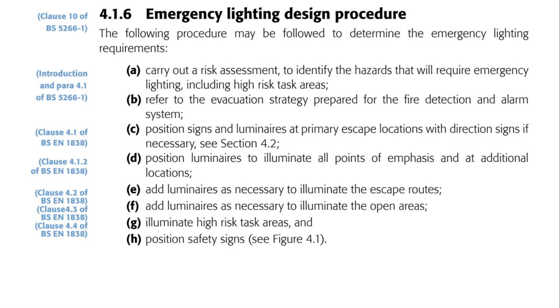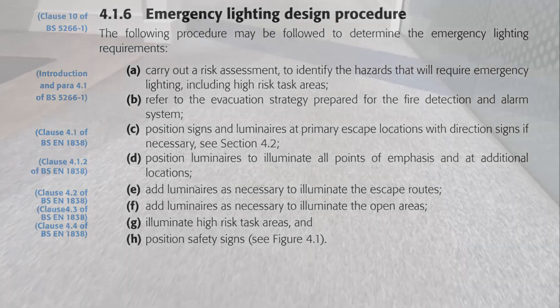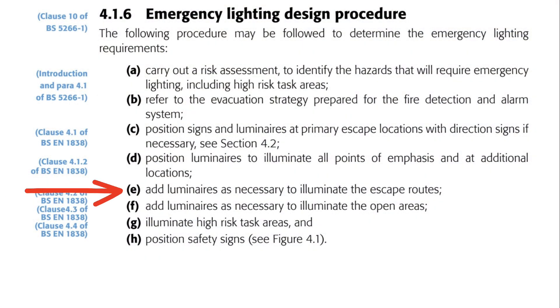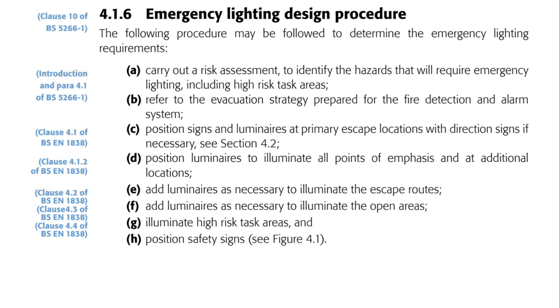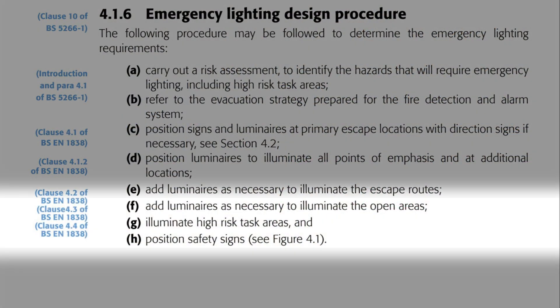Speaking of escape routes, that brings us back to the design procedure. Escape route lighting is critically important, but we only add it after the other elements because once those are placed, we may have already achieved the required lighting levels for the escape routes. If not, we add emergency fittings to bring it up to the right level. Following the same principle, we then add open area emergency lighting, high risk task area lighting, and position any safety signs.